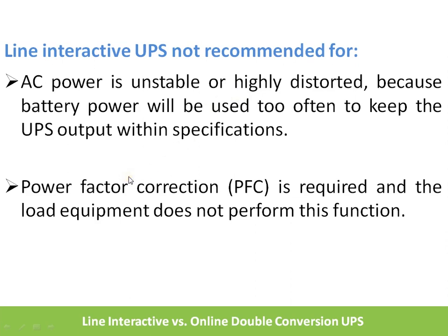This increases the running cost of the UPS. And whenever power factor correction is required for your application and the load equipment to which your UPS is going to connect does not perform this function, then this line interactive UPS is not recommended, because a line interactive UPS does not have inbuilt power factor correction.